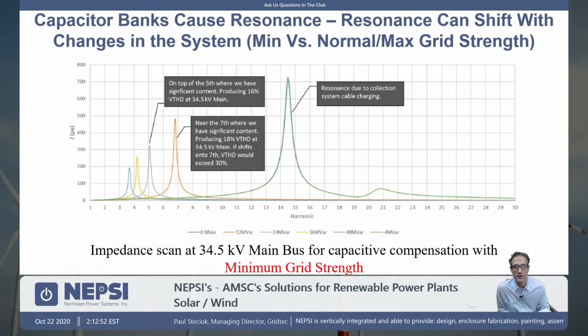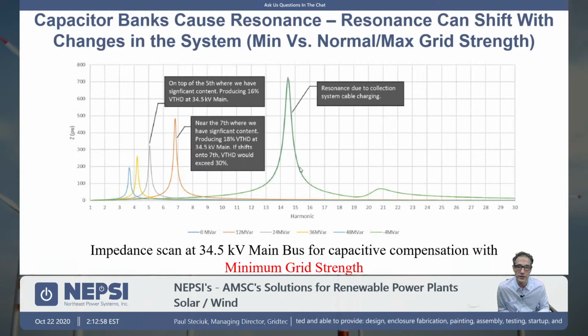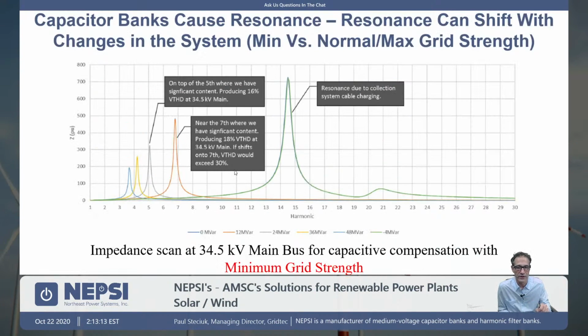We'll develop the impedance scans, and here you can just see the classic impedance scan. We have the system here in the green before we put any capacitor stages on. We have a resonant condition. The collector system, along with any filter that might exist inside the wind turbine, will create some type of resonant condition in the system. This, of course, becomes a concern for the condition where we have nothing online.